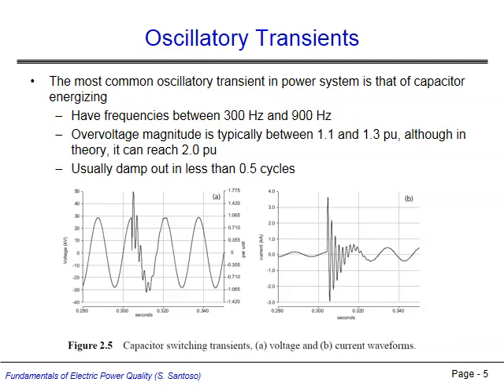Most often, oscillatory transients are caused by the switching of capacitor banks. These transients have frequencies between 300 and 900 Hz, produce voltage spikes between 1.1 and 1.3 per unit, and damp out in less than half a cycle. The figure shows the voltage and current waveform characteristics of a capacitor switching transient.